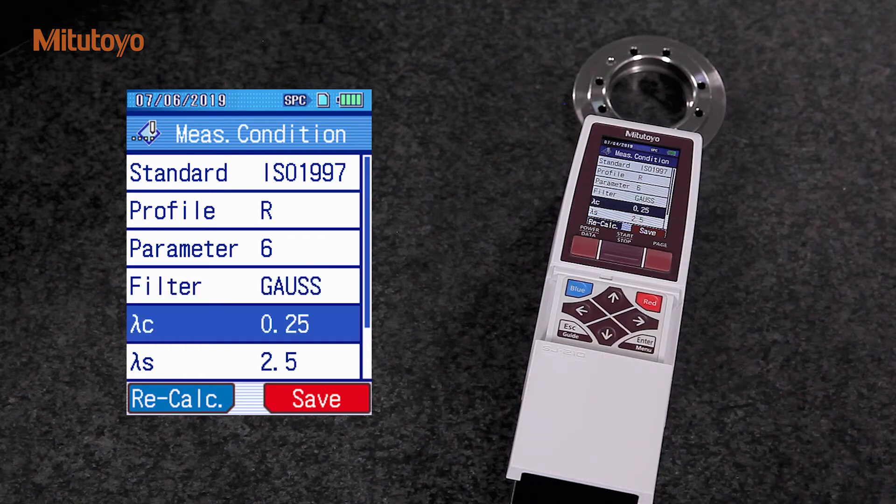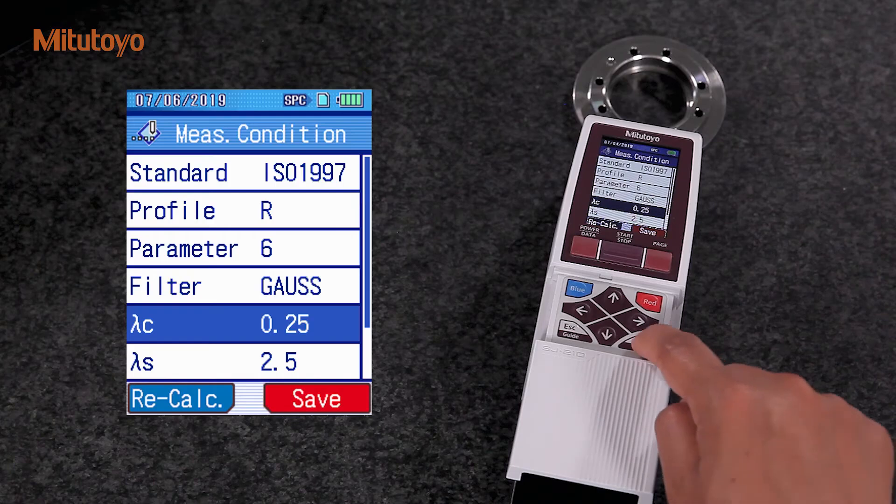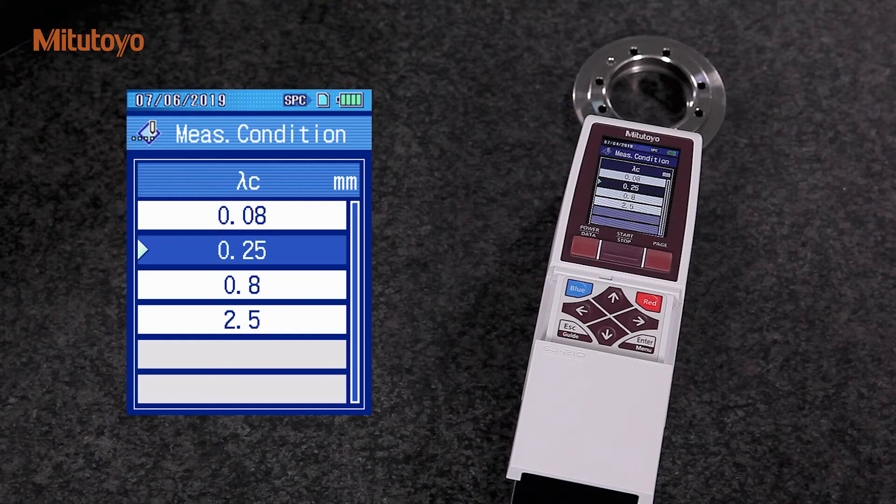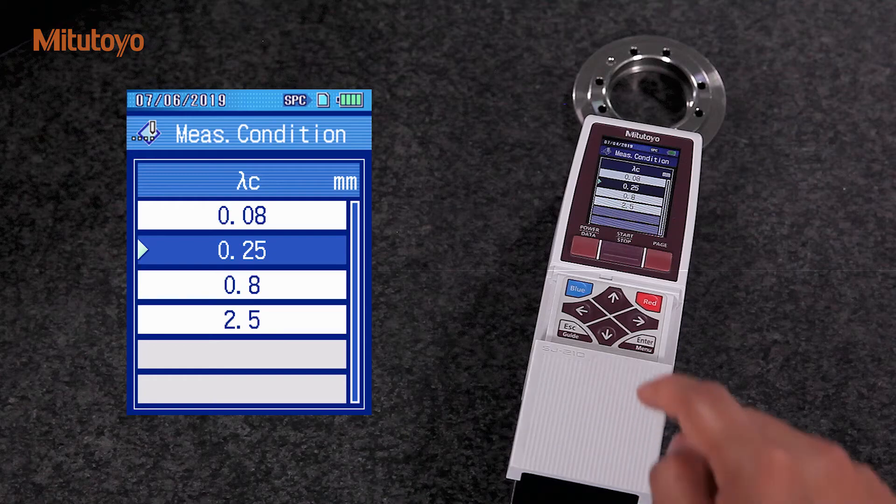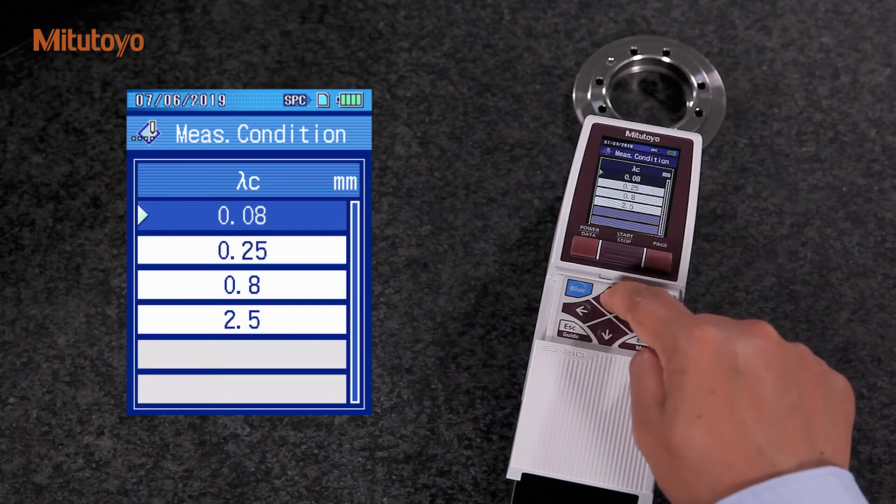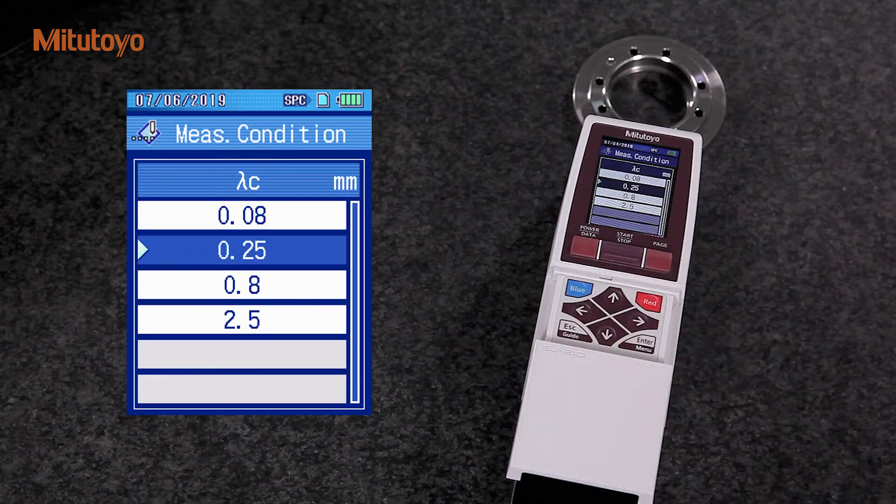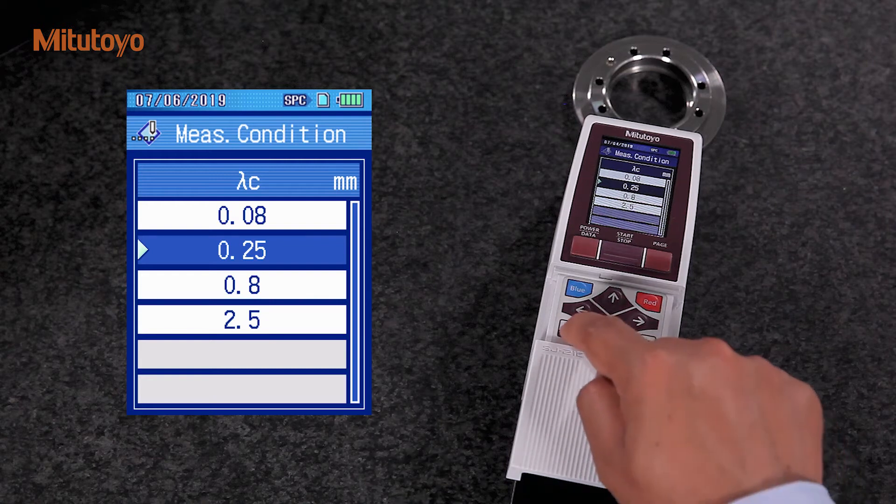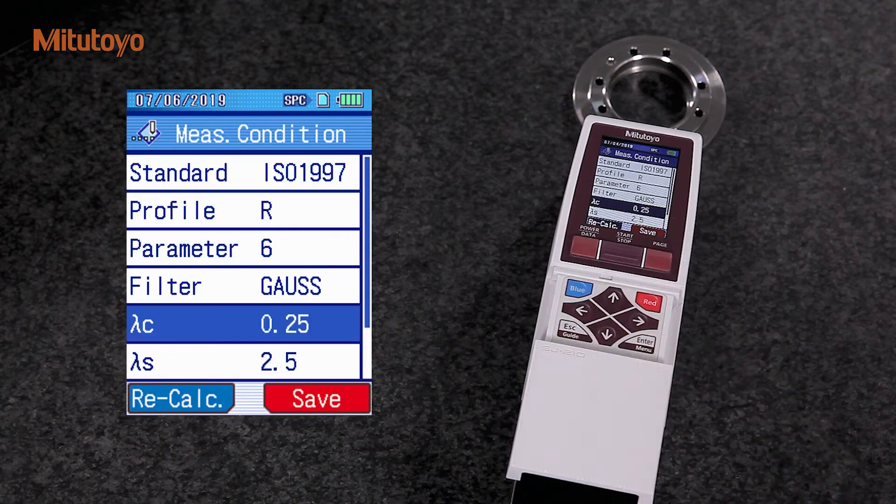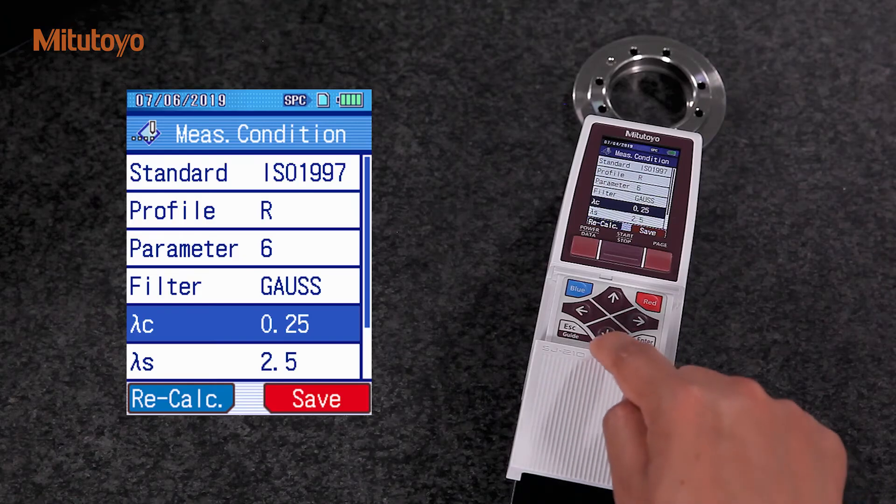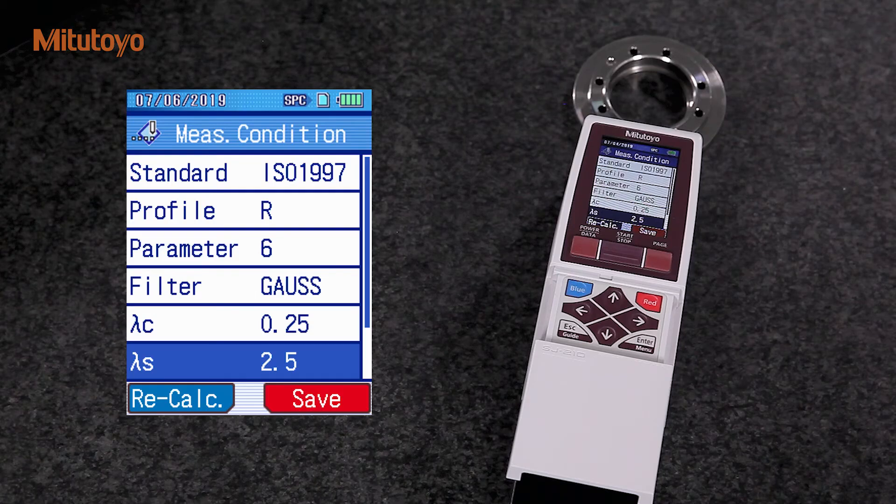Lambda C is the filter setting. This is one of the most important settings for roughness measurements. The selection of filter we apply depends upon the tolerance mentioned in the technical drawing. ISO 4288 provides us with the guideline for selecting the required filter. In this case, I will use 0.25. The SJ-210 automatically chooses Lambda S according to our selected Lambda C.